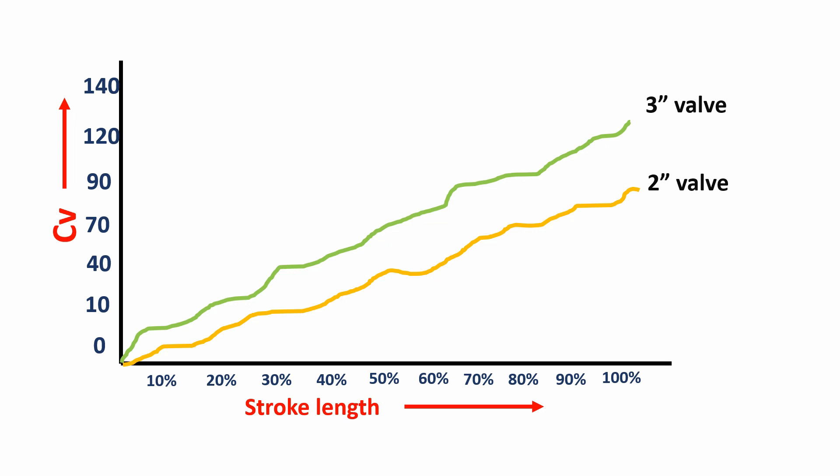So how do these manufacturers select the Cv? Basically there is a hard and fast formula that you select the Cv which falls between 20 to 80 percentage of a control valve stroke length.